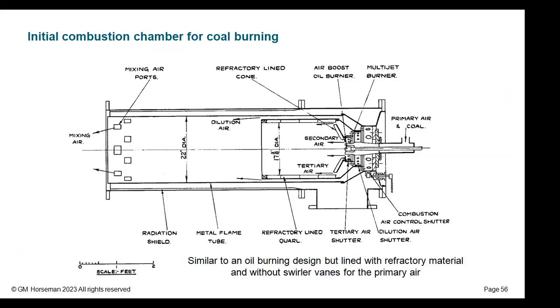The combustion chamber had to be different. And one of the key differences was you couldn't have swirlers before the burner. There had to be none. If you create a swirl, all that would happen is the coal particles would be centrifuged out to the outer boundary and would just form slag. So this is what was designed. And again, the other change was the introduction of refractory material inside the flame tube.